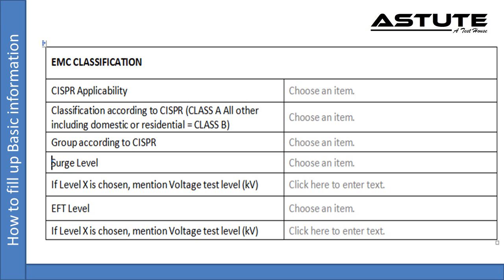Level 5. Special situations to be analyzed. The minor or major electromagnetic separation of disturbance sources from equipment circuits, cables, lines etc. and the quality of the installations may require the use of a higher or lower environmental level than those described above. It should be noted that equipment lines of a higher environmental level can penetrate a lower severity environment.